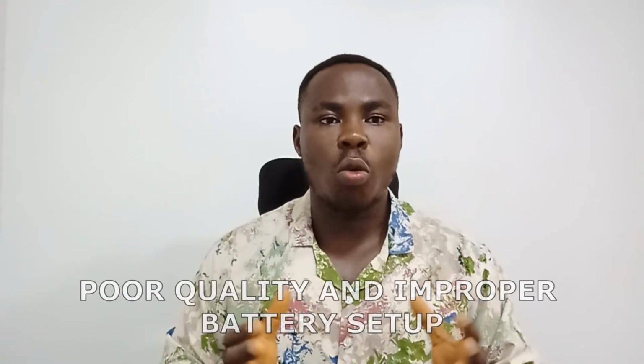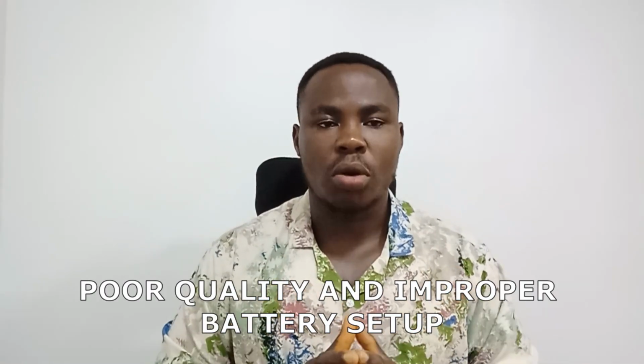Number 5 is poor quality and improper battery setup. Your batteries can catch fire if overcharged or over-discharged without a proper battery management system, if installed in a poorly ventilated environment, and when there is loose connection or cable short circuits in your batteries. Therefore, make sure that your battery connection is tight and avoid cable short circuiting. Make sure that your battery is installed in a well ventilated environment, and also avoid overcharging and over-discharging of your batteries to avoid fire outbreak.